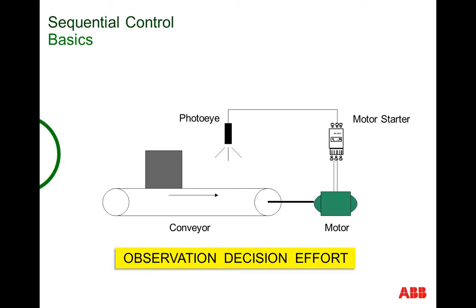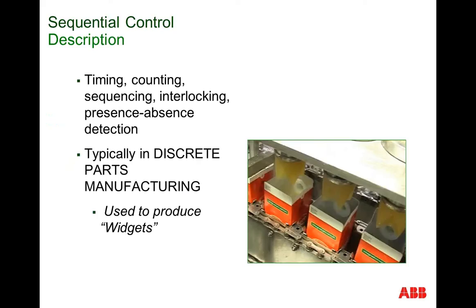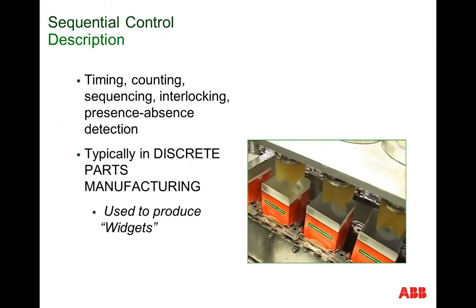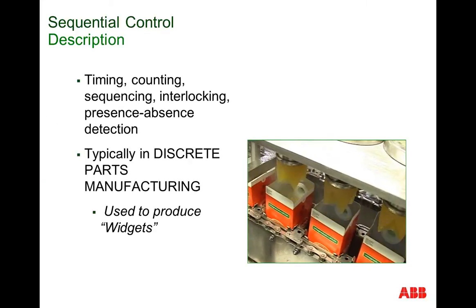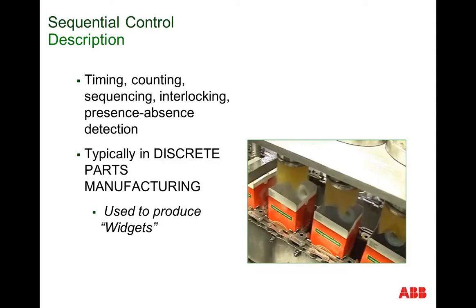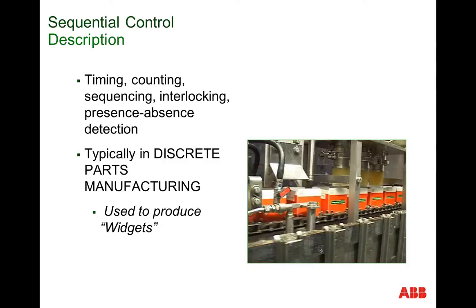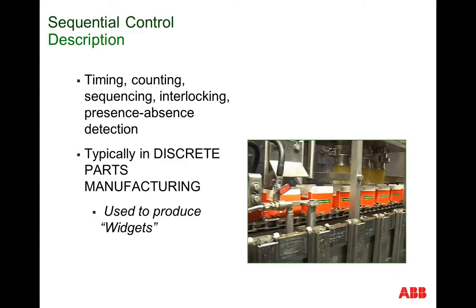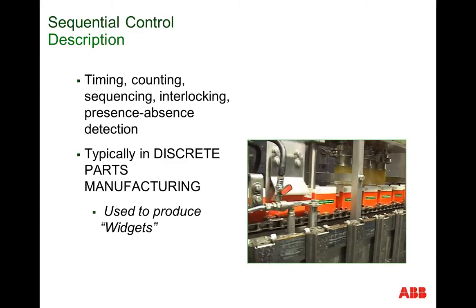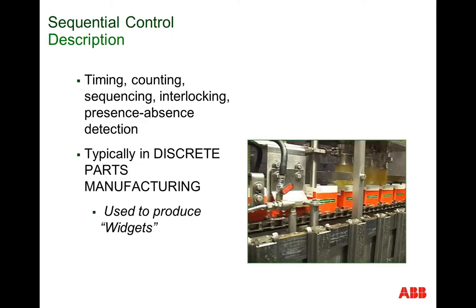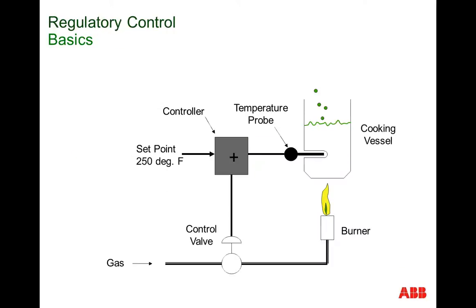Now, let's start with sequential control. Here's an example of a box on a conveyor. A photo eye observes the conveyor and trips off the motor starter when the box breaks the beam. Notice the closed loop here: observation, decision, and effort. Sequential control consists of typically hundreds of these observations, decisions, and outputs. Sensors and controllers perform timing cycles, the counting of parts, the sequencing of manufacturing steps, and the interlocking of systems so that parts get produced in the proper sequence and at the proper speed. Sequential control is typically found in discrete parts manufacturing, or essentially the making of widgets.